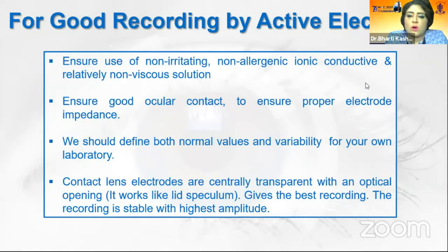For good recording by active electrodes, ensure use of non-irritating, non-allergenic, ionic, conductive, and relatively non-viscous solution. Ensure good ocular contact to ensure proper electrode impedance. We should define both normal values and variability for our own laboratory.